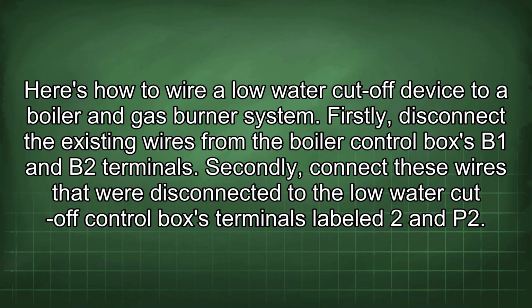Here's how to wire a low-water cut-off device to a boiler and gas burner system. Firstly, disconnect the existing wires from the boiler control box's B1 and B2 terminals. Secondly, connect these wires that were disconnected to the low-water cut-off control box's terminals labeled 2 and P2.